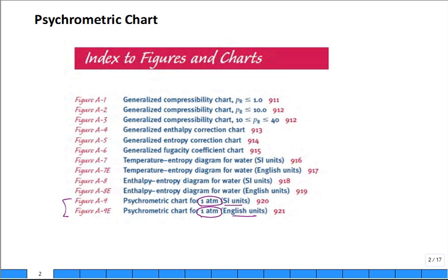But if you start going at different elevations, because it becomes lower overall total pressure, you just move to the computer, and the computer programs can take care of the exact elevation. If you needed to design something for 12,000 feet, some high elevation, that's the way you would do it. But don't forget that these psychrometric charts are for sea level, and there are a lot of people living and operating around sea level.